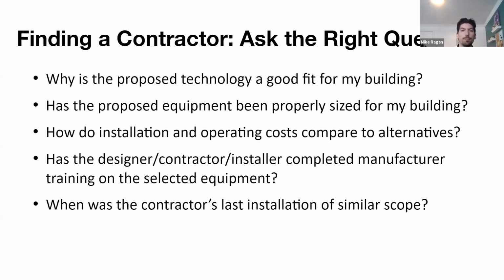It's an excellent question. Has the proposed equipment been properly sized for my building? This is an excellent, excellent question that everyone should feel empowered to ask, to make sure that we've properly accounted for the derates associated with your climate. Last thing we want is, on a design day situation where everyone needs the full amount of heat in the system, our outdoor unit wasn't sized accordingly and its derate is only able to deliver 70% of its heating capacity. If you need 80% of the heating capacity, you're going to fall short. So we want to make sure it's been properly sized.